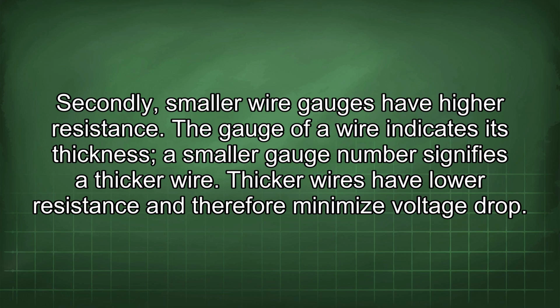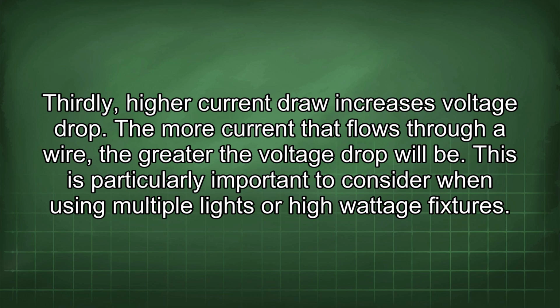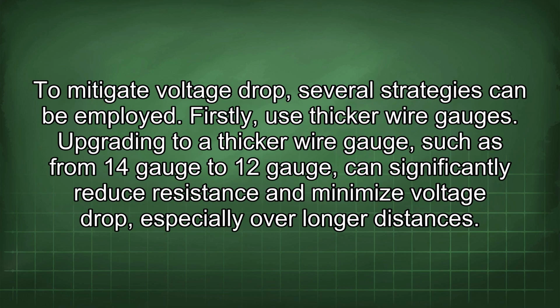The gauge of a wire indicates its thickness; a smaller gauge number signifies a thicker wire. Thicker wires have lower resistance and therefore minimize voltage drop. Thirdly, higher current draw increases voltage drop. The more current that flows through a wire, the greater the voltage drop will be. This is particularly important to consider when using multiple lights or high wattage fixtures. To mitigate voltage drop, several strategies can be employed. Firstly, use thicker wire gauges. Upgrading to a thicker wire gauge, such as from 14 gauge to 12 gauge, can significantly reduce resistance and minimize voltage drop, especially over longer distances.